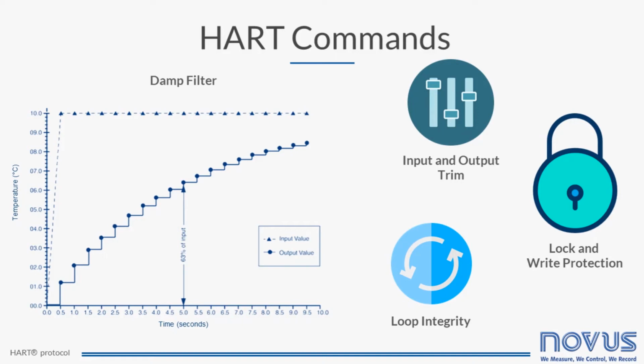Lock and write protection. Lock is a command that temporarily locks a device, preventing any parameter change from a local panel or a secondary master. In this case, the HART primary master has exclusive access when configuring or calibrating the field device. The write protection, on the other hand, is a device-specific command that puts the field device in a reading state, which means no write commands accepted. Only reading commands are effectively executed.